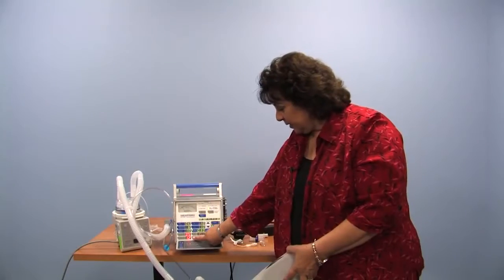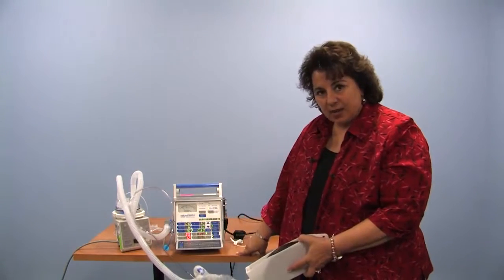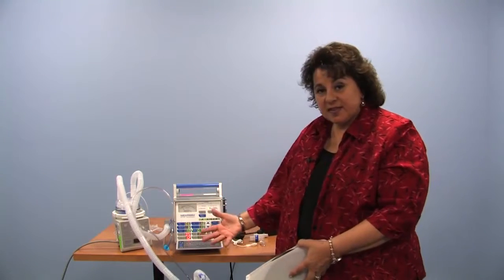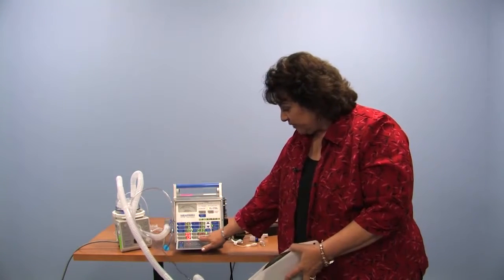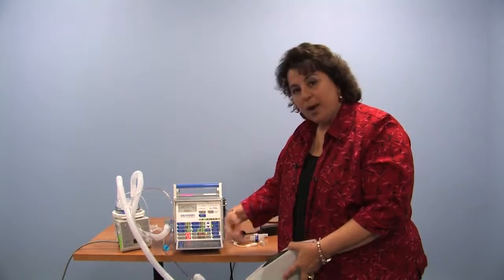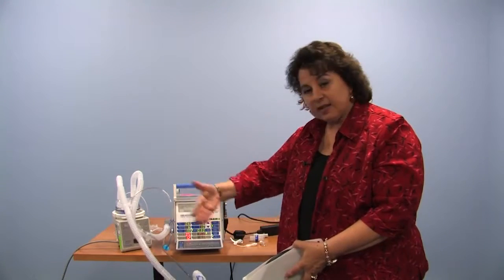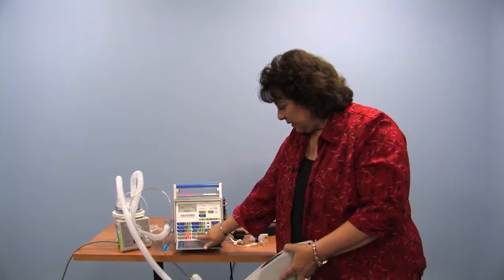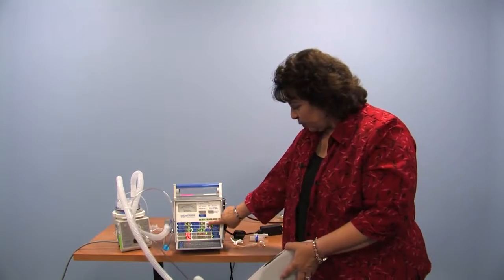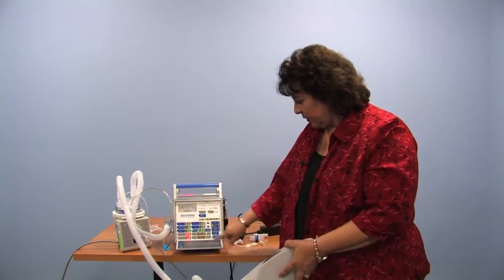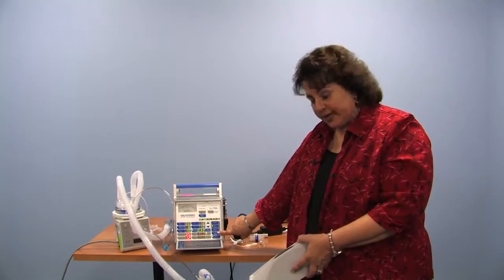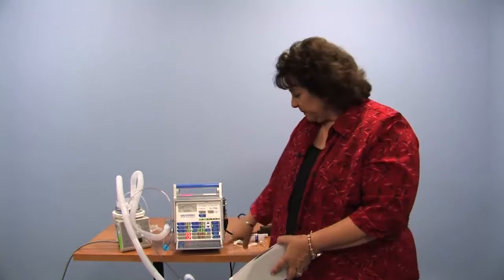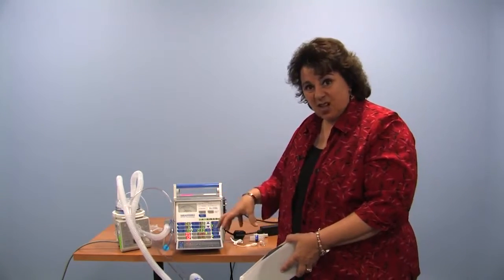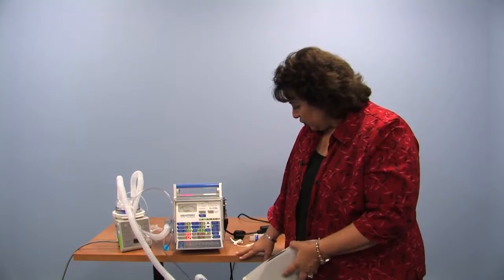So half a liter, or 0.5, is the low alarm setting, and 15 is the high alarm setting. This is the way it was designed. When it's not flashing, you're seeing the actual amount of air in a minute that the machine is sending to your child. If you push the button, it flashes, and those are the alarms, which can be adjusted again with the arrow. Everything is adjusted with the arrow. But as we talked about earlier, it can be locked with an internal menu, so you would hold the button for 5 seconds to unlock it and be able to make a change.